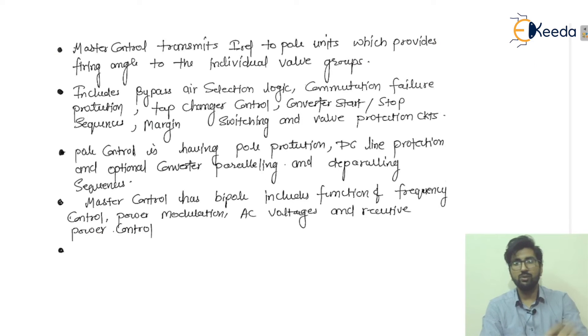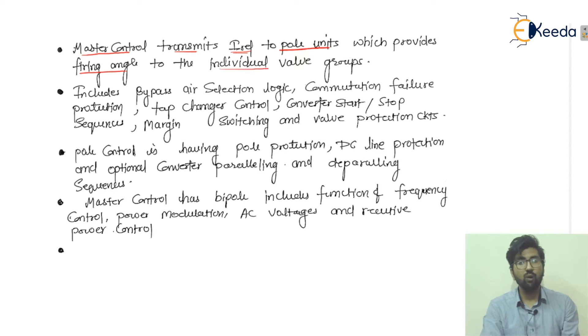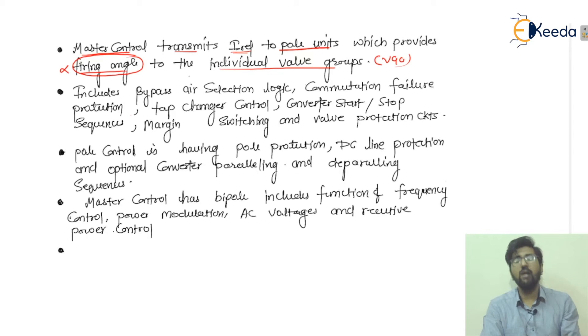The master control transmits the I_ref, the reference current, to the pole units. The pole units provide the firing angle to the individual valve group, which is the VGC — the valve group control. So from pole one and pole two, the signal goes to the VGC, which provides the value of the firing angle alpha.